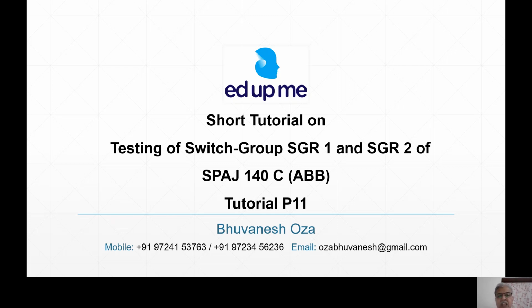Here in this relay there are two groups available, and as I was telling, there are as many as 6 groups available in the recent most numerical relays. So that was the facility in SGB 5. SGB 6 and 7 were latching, that is hand resetting of the trip signal. So these were the facilities in SGB, that is switch group blocking.